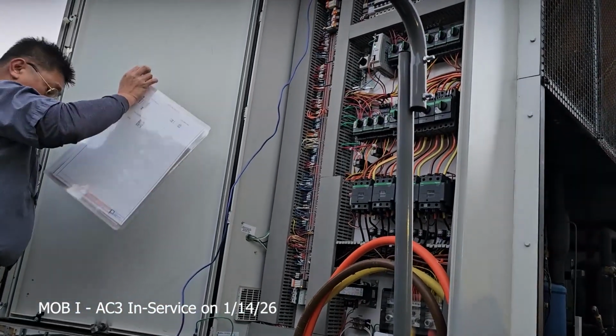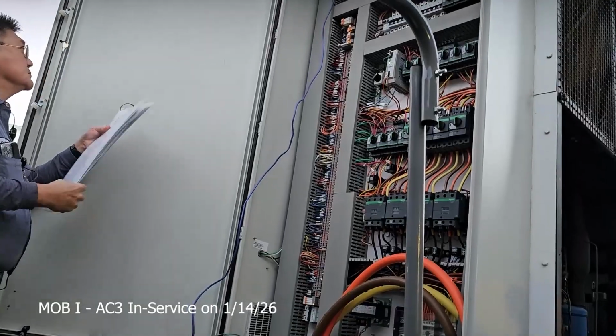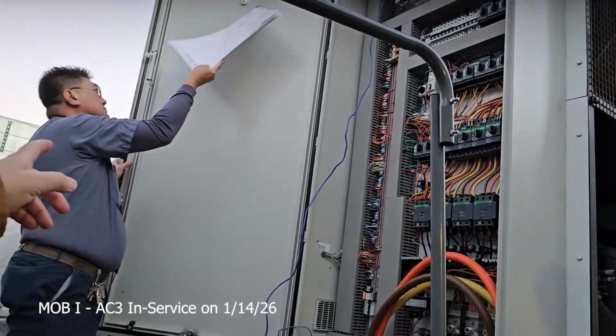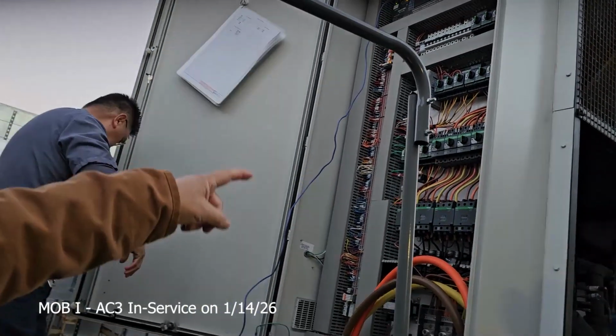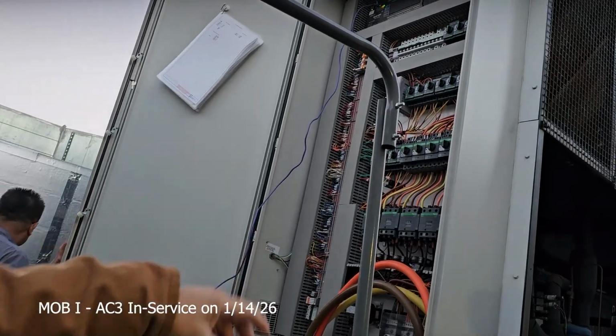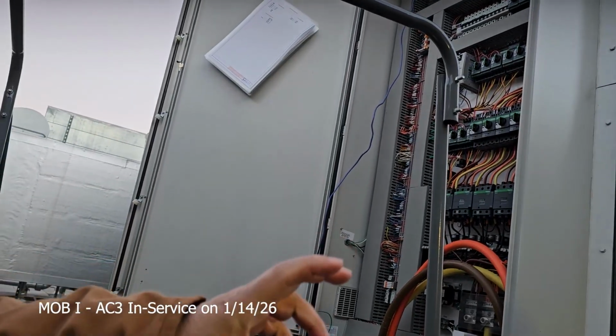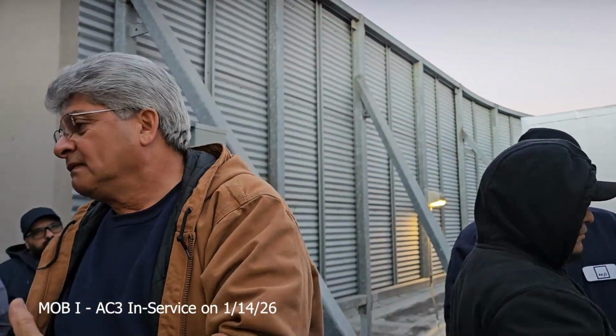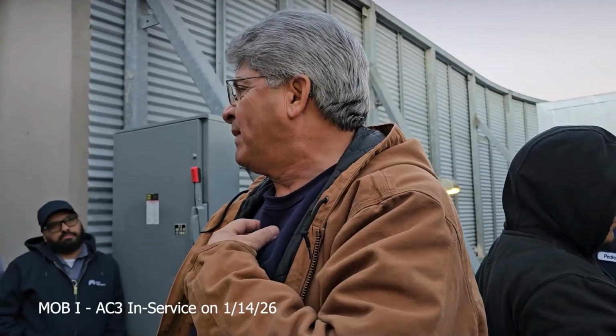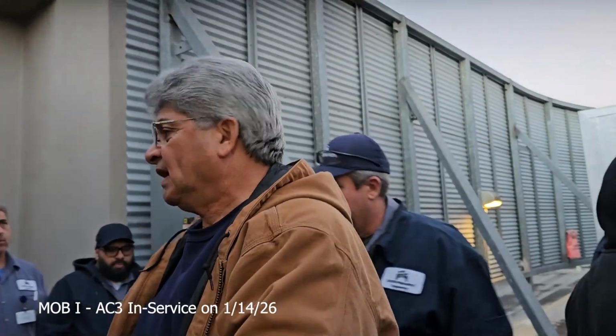You've got a full complete wiring diagram on each machine. These 4 are for your compressors. You turn them off, you turn them back on again. That'll reset the oil alarm. Vireo can do it remotely. I don't have that. They didn't want us to have that capability of being able to dial in remotely and see what you have for alarms and reset stuff. So those 4 breakers are a manual trip.